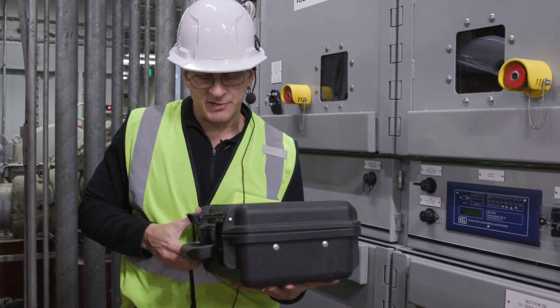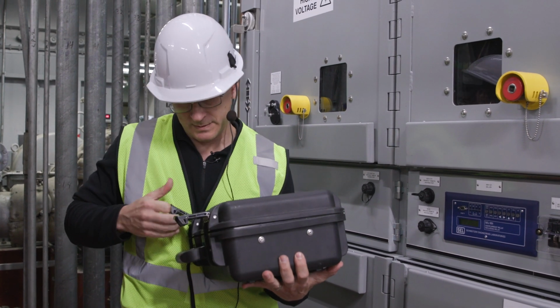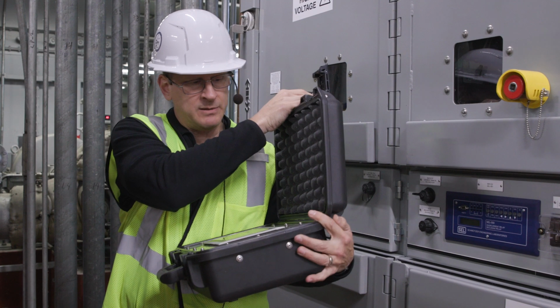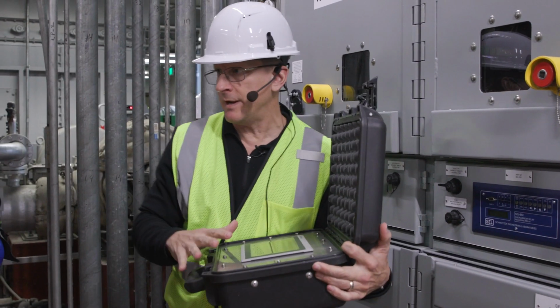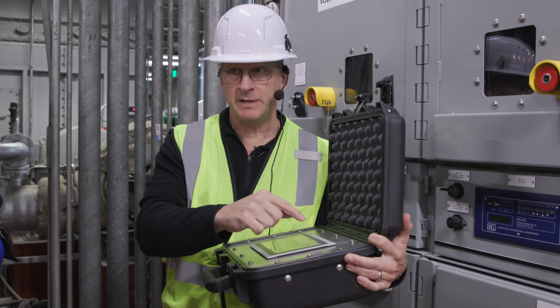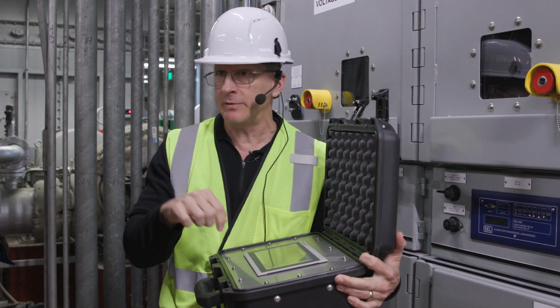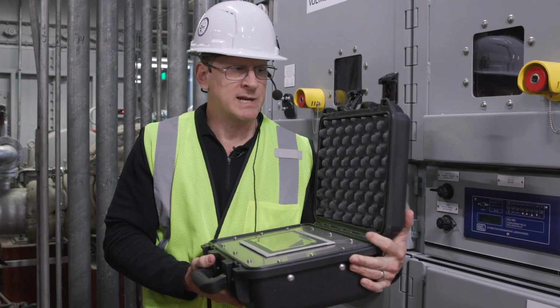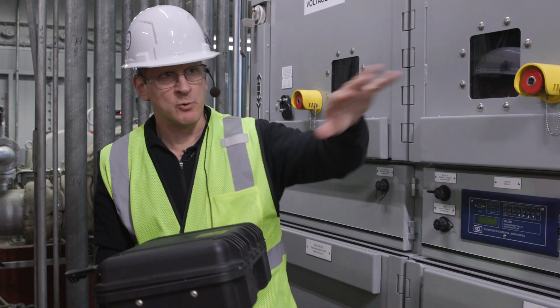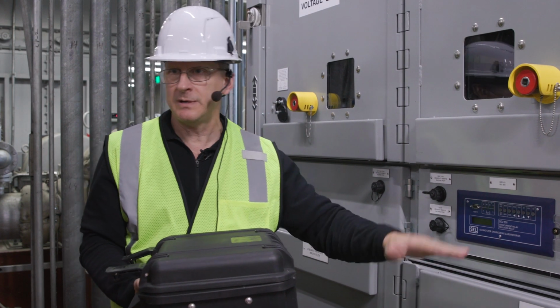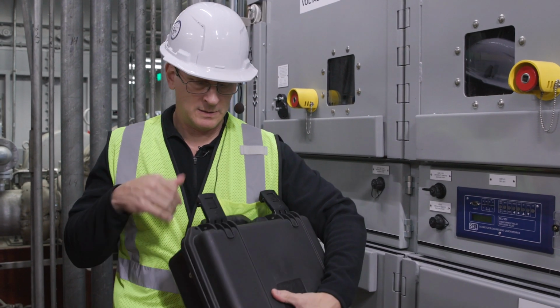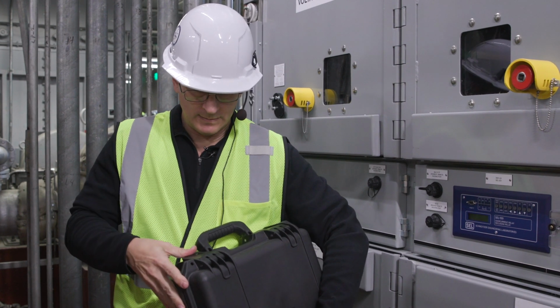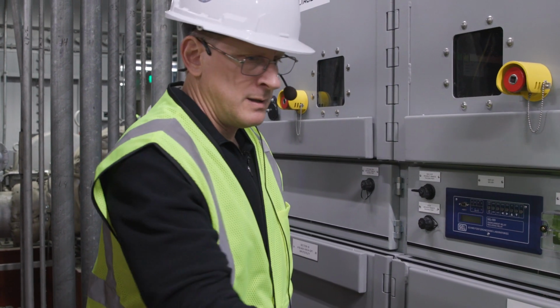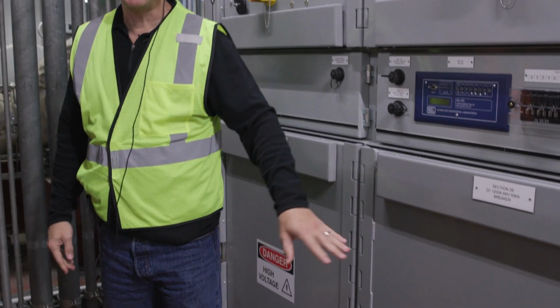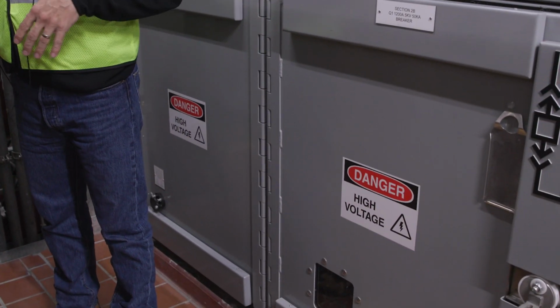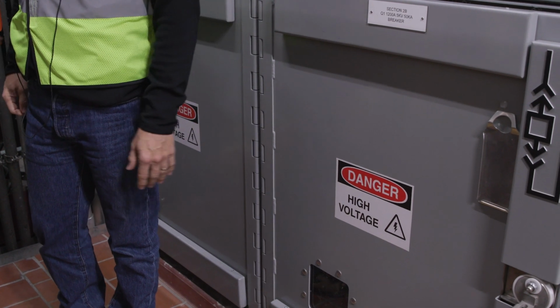We can't do it now because everything's shut down, but basically, once you plug this box into these ports, this comes alive, and it gives you push button indications that allow you to manually rack out the breakers or rack them in. So you can actually, with the cord, do it around the corner if you want. You don't have to stand in front of the breaker to rack it in and out. It's a very nice system. Of course, you can always manually do it as well if you're forced to, but it's quite a chore. It takes a lot of effort to rack in and out these breakers.